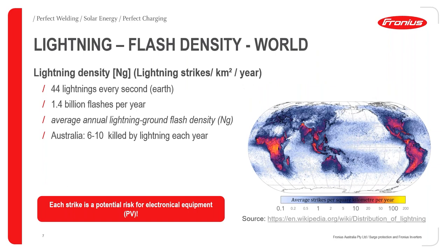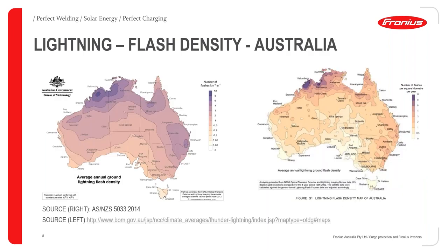Looking at flash density globally, Australia is not the worst compared to the world, but on average 6 to 10 people are killed by lightning every year in Australia. In the PV industry, this is relevant. The flash density map from the standard AS/NZS 5033:2014 has actually been updated — the flash density has increased for Australia and the standard will likely be updated in a future version.